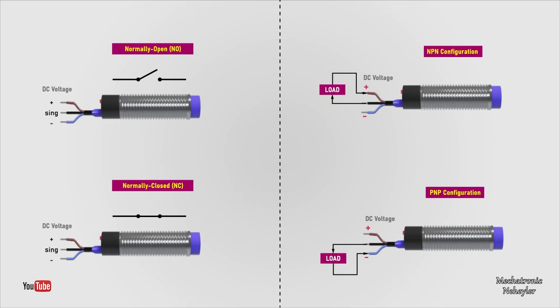Another configuration is that the sensor can be NPN or PNP. For this case, I am considering sensors powered by direct current voltage, but there are also alternating current ones. They usually have three cables: the brown wire connects to the positive power supply, the blue wire connects to zero volts or negative power, and the black wire is where we get the signal from the sensor, which connects to the load — which can be a relay, a PLC, or any other controller. In another video, we will detail the connections that need to be made.